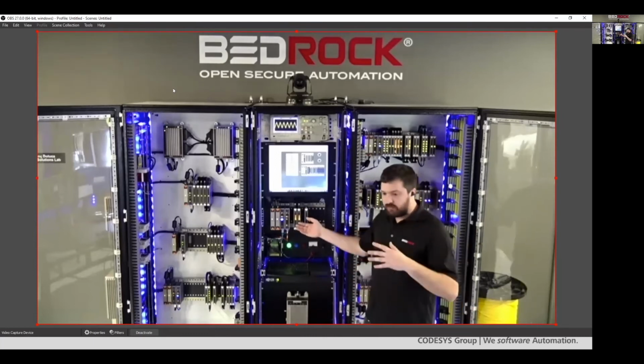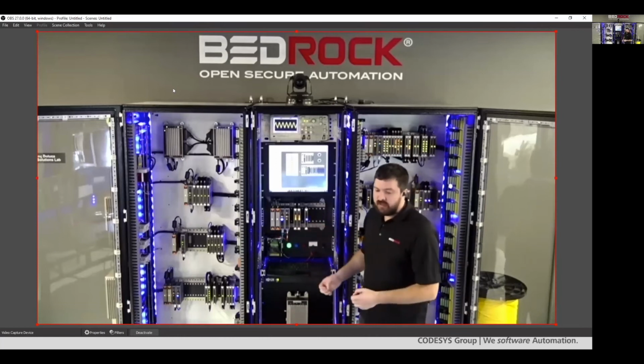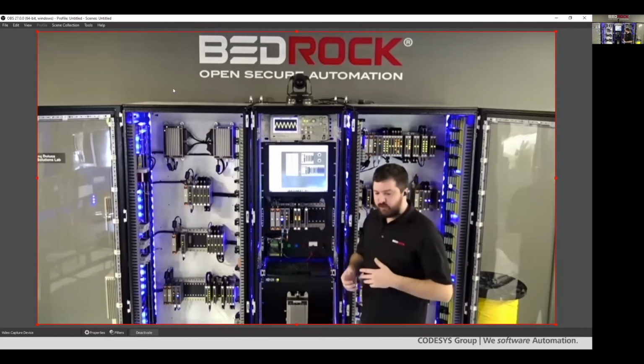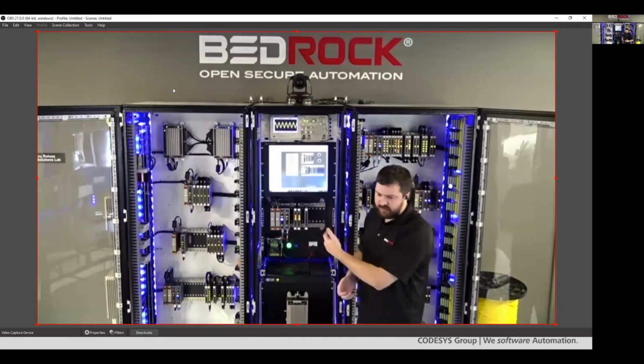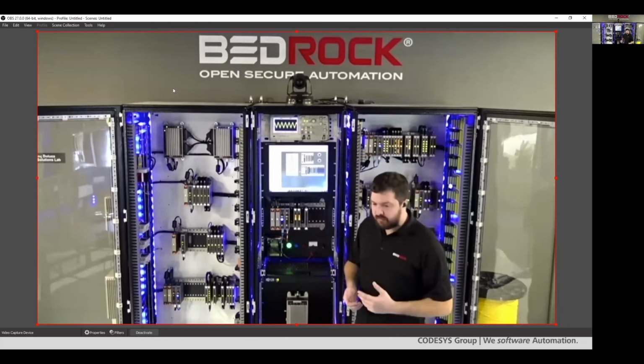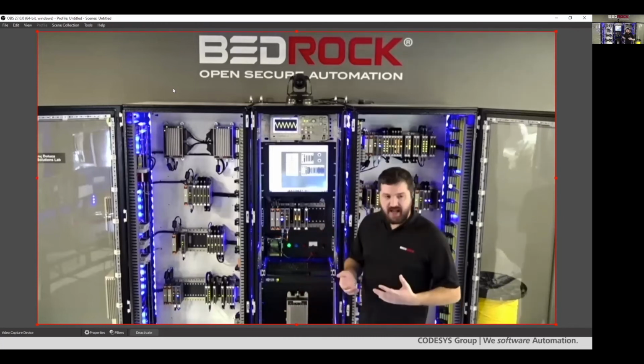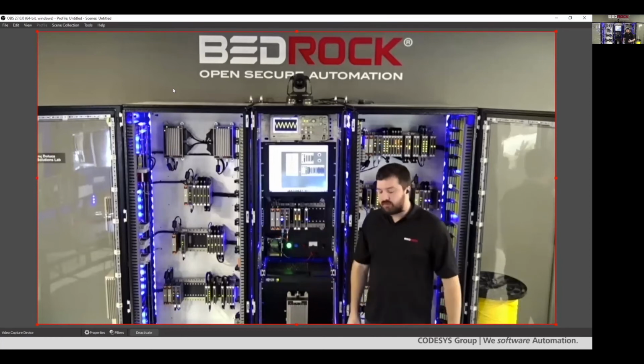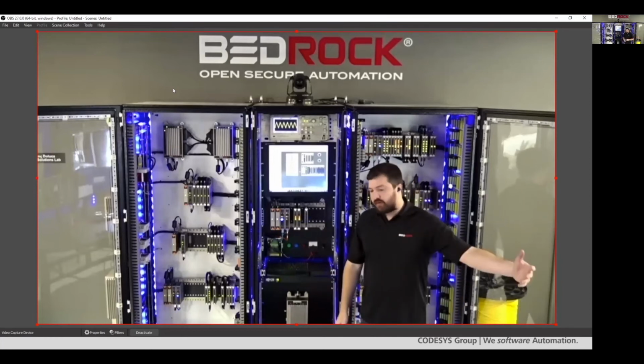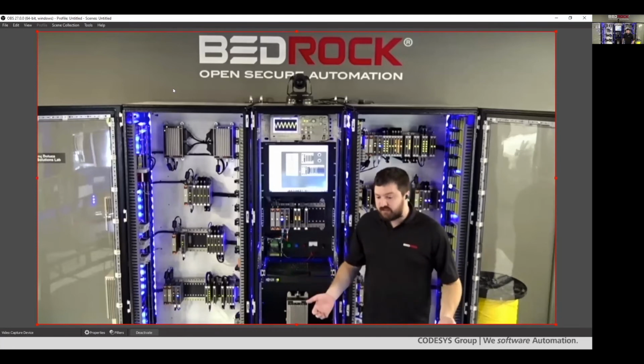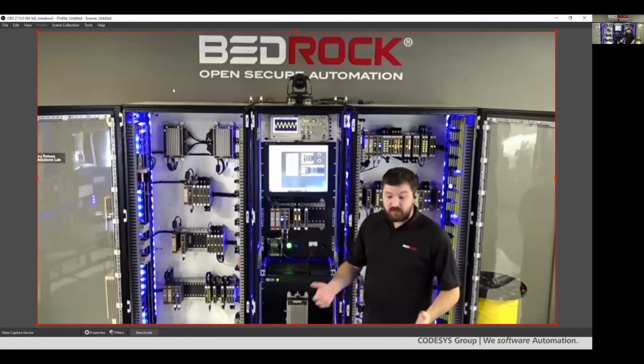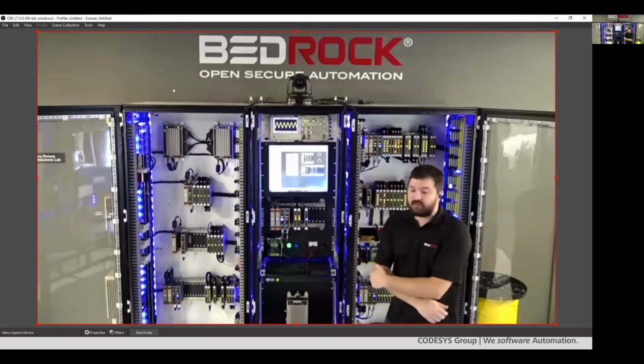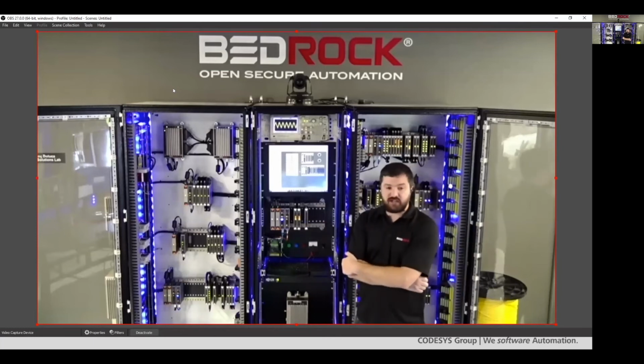You can extend that into the IEC code and create these quick visualizations that allow you to do IO checkouts and commissioning while still having your primary SCADA connect back up to whatever main SCADA server you're using. A huge benefit you get with that, for security reasons, is it actually gives you local control access.